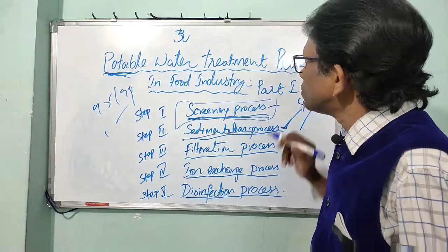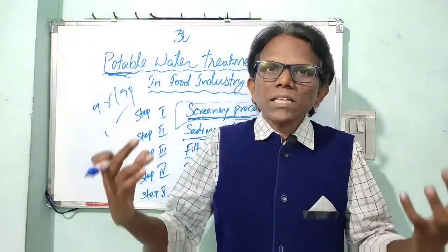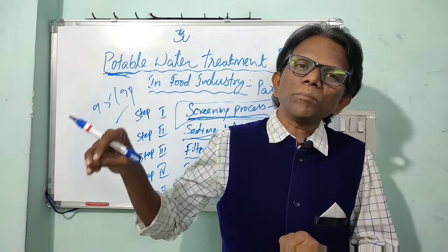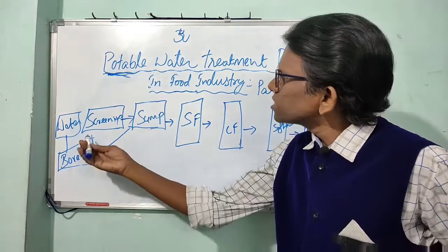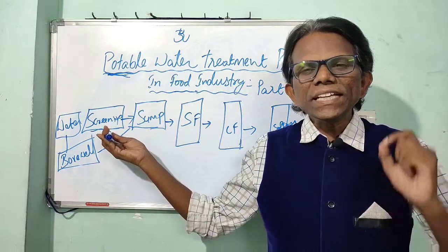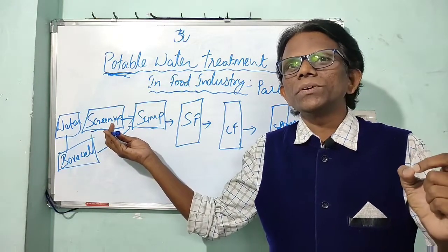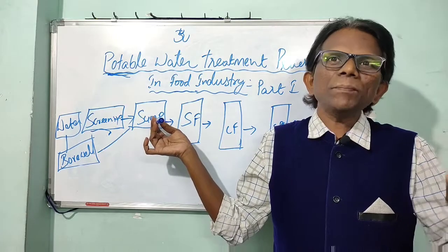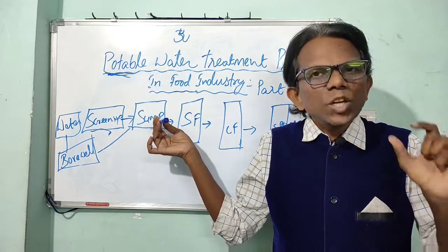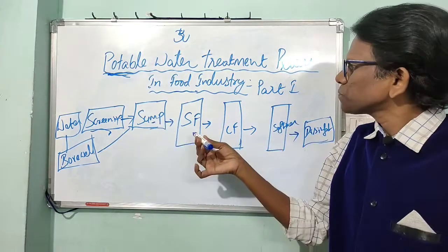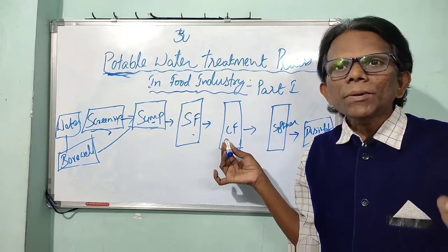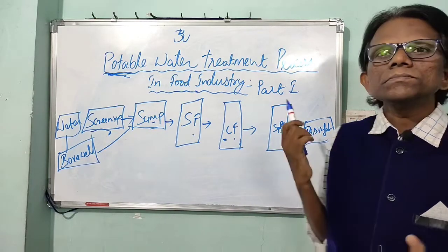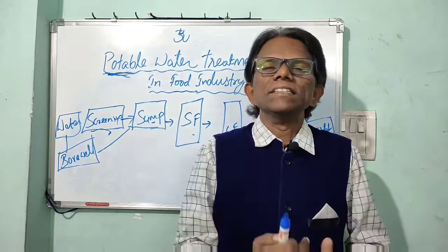After two to three hours, once the suspended particles settle to the bottom, we take the supernatant water for further processing. Sedimentation plays a crucial role because water contains many suspended particles that can easily be removed by settling. In the screening process, floating impurities are removed. In sedimentation, suspended particles are removed by keeping water undisturbed in a deep tank. In filtration, a sand filter or activated carbon filter removes colloidal particles. In disinfection, microbes are killed and removed.